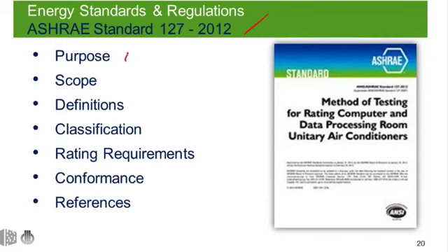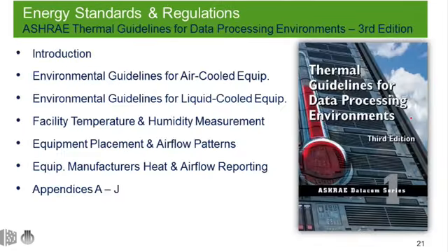ASHRAE Standard 127, the purpose, the scope, definitions, so forth, this has to do with unitary air conditioning equipment. And this is an important standard for us because the equipment that's used for a data center has a totally different sensible heat ratio. And so that's where this standard becomes really important, and it's good to reference it if you're working on a data center.